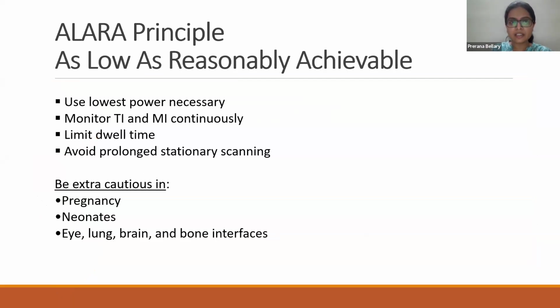So what we can do to reduce this is go by the ALARA principle, which is as low as reasonably achievable. What that means is we have to use the lowest power possible, monitor the thermal index and the mechanical index continuously, limit dwell time, and avoid prolonged stationary scanning.